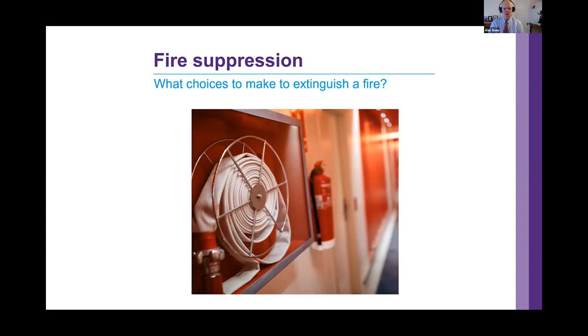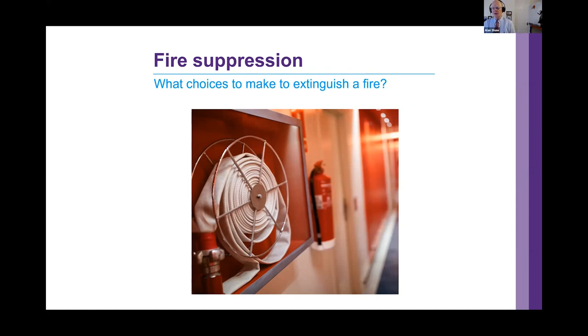We can answer questions on alarm volumes in the Q&A session. In this instance, we've got a hose reel. Personally, I believe they can only be used successfully by a trained fire brigade officer, or somebody who has had a lot of training and knows what they're doing. Too often I see them next to a 415-volt electrical panel, and that's stupid. Very often they will run through a door and be a breach of compartmentation or a trip hazard. Here we have a hose reel that was probably put in a long time ago. These can often be found in old offices and warehouses, and often in cupboards that have been forgotten.